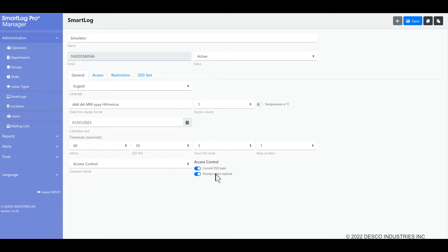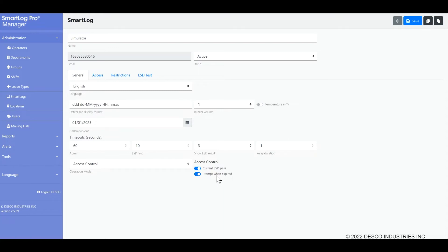Prompt when expired is one of the other options. When enabled, operators with a fail or not tested status will be allowed to perform an ESD test in order to be granted access. If they pass, they will be granted access moving forward. If they fail, they will be allowed to retest. When disabled, operators will be required to perform an ESD test at a different SmartLog Pro SE and obtain a pass before being granted access on this specific tester. Yes, that means that you will not be permitting the ESD test on this tester. You have to do it on another unit.